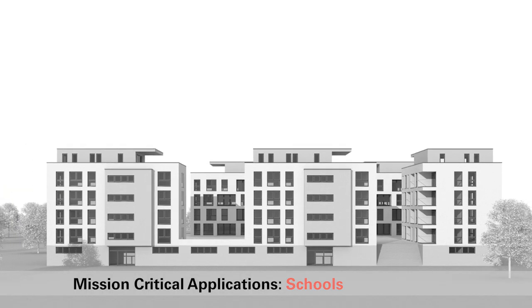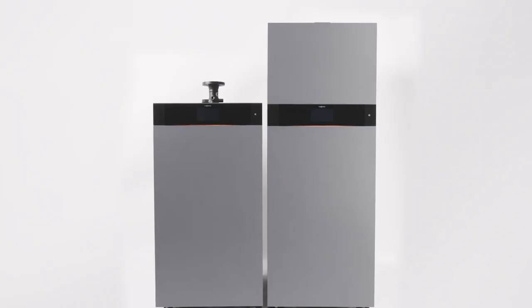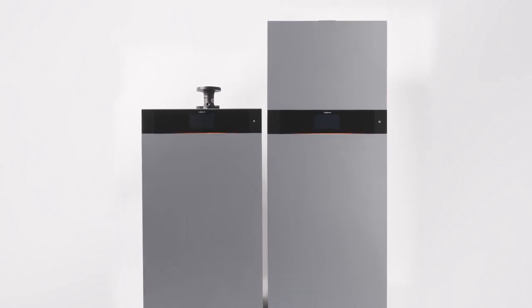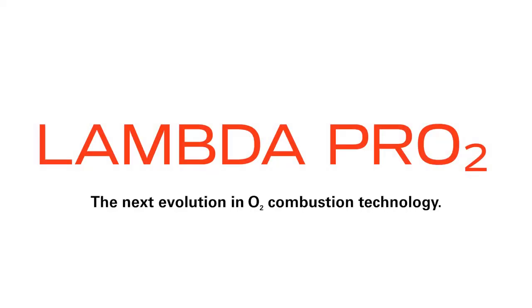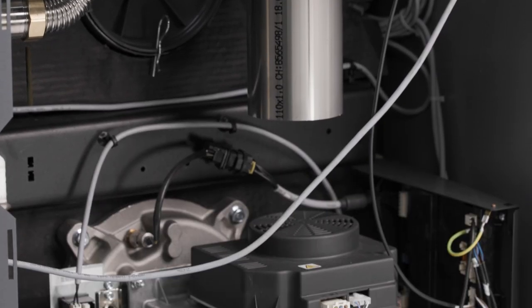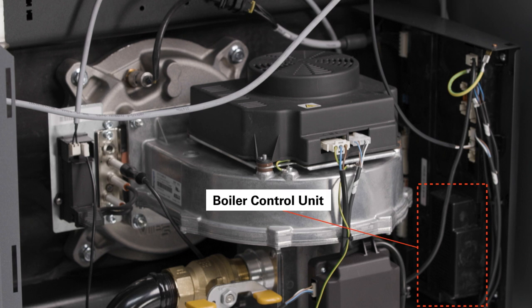Designed for schools, hospitals, municipal infrastructure, and other mission-critical applications, the Vitocrossal 200 CI2 utilizes the industry's most advanced active O2 combustion control — Viessmann's Lambda Pro2, included standard in all capacities. Lambda Pro 2 begins with a durable O2 sensor which is auto-calibrated to environmental conditions every 60 seconds and requires no cleaning and no manual calibration.